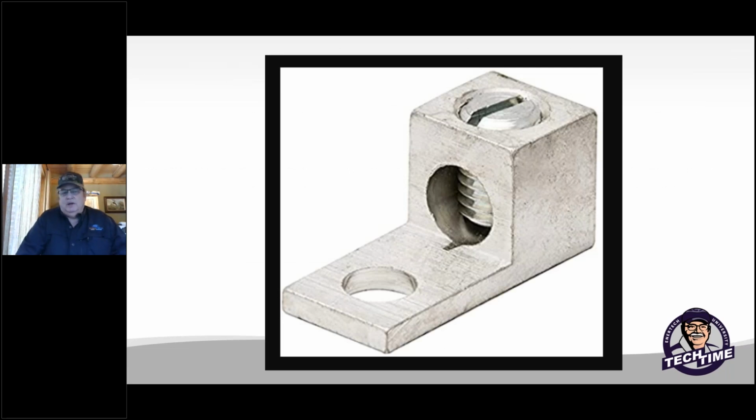On a typical grounding lug, you see the hole where we would screw it into the cabinet. Pay attention to that as well, because I also find that if that grounding lug is placed on, let's say, a painted surface, sometimes we don't get really good contact. I've done this even on ice machines: scrape the paint off the back, put the screw back in, so I get myself a better ground. That's something important to pay attention to on your technical service calls, repairs, etc.